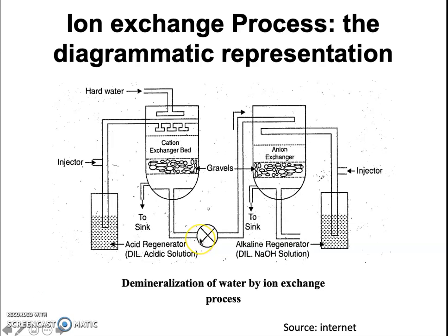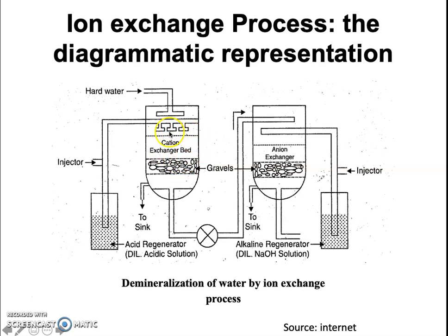Now let us see the diagrammatic representation of this process. This is how the ion exchange process is carried out. This is the cation exchange bed — you can see the gravels, the big pebbles or stones present in this cylindrical container. The purpose of these gravels is to support the cation exchange bed. This bed contains negatively charged functional groups which help to trap the cations present in hard water. When hard water is first allowed to pass through the cation exchange bed, all the cations get trapped into the resin, and the water coming out contains H⁺ ions and all the anions initially present in hard water.